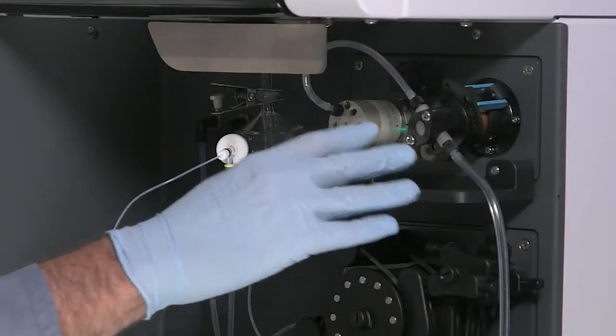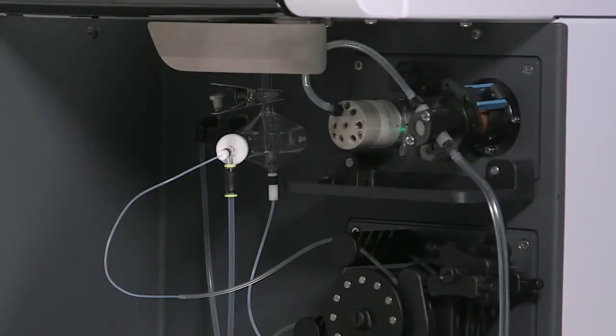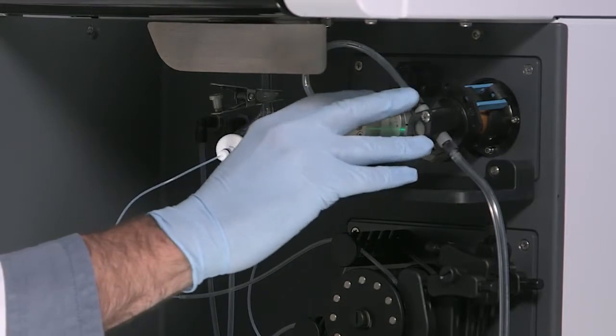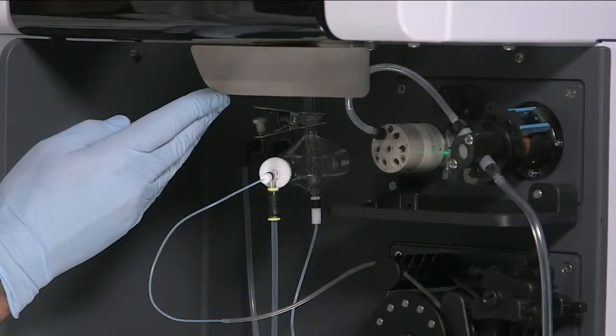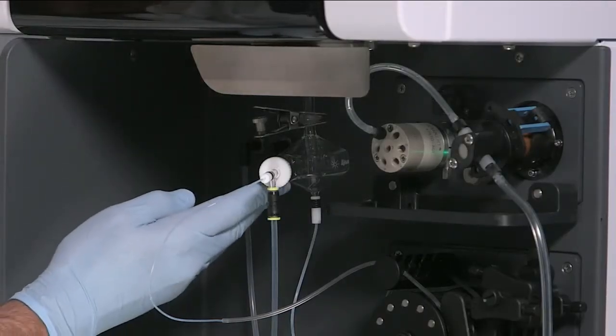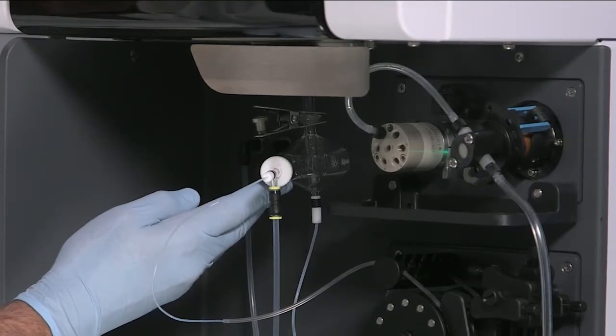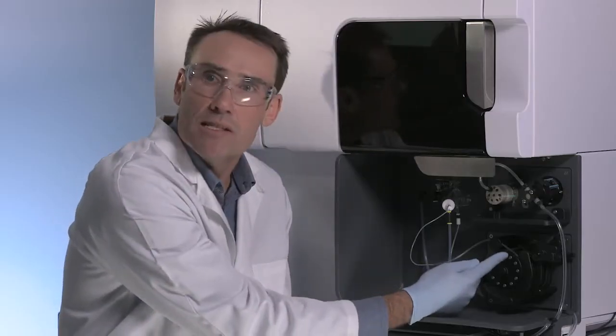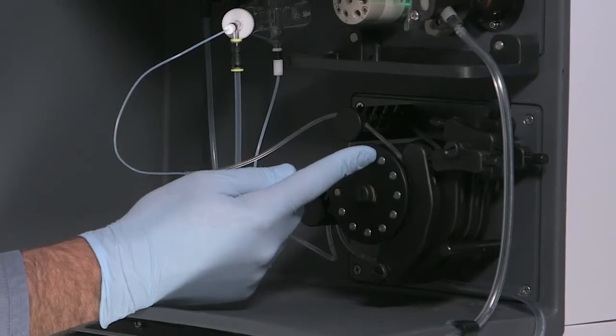The advanced valve system's located above the peristaltic pump. Can you talk to us about how that simplifies the customer's workflow? So the new fully integrated advanced valving system is tucked up here out of the way. This is intentionally put in this position so we can completely eliminate physical obstruction with the important sample introduction components. We have easy access to the torch, we have easy access to the spray chamber and nebulizer assembly, and we have easy access to our peristaltic pump tubing.